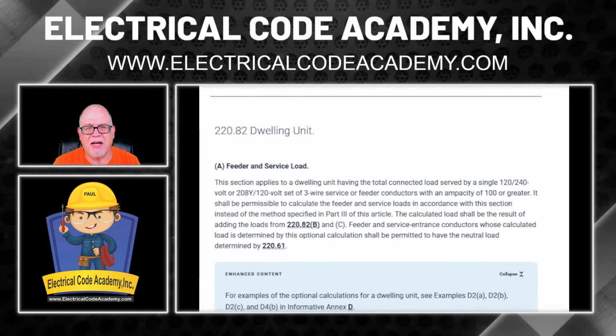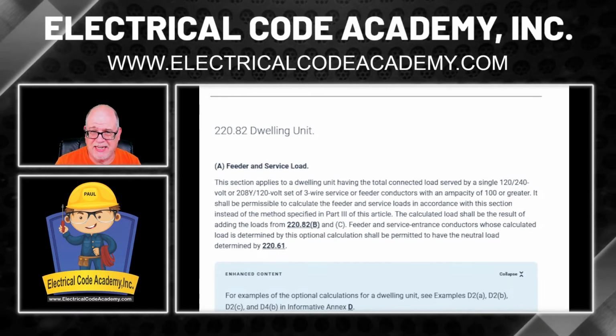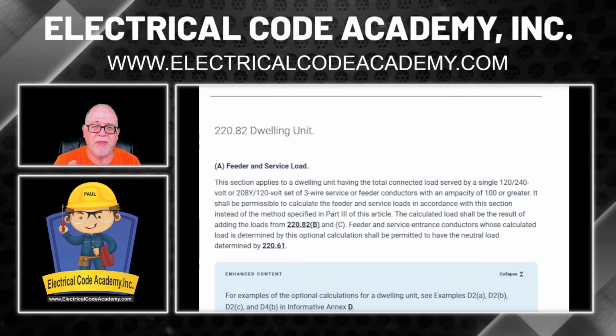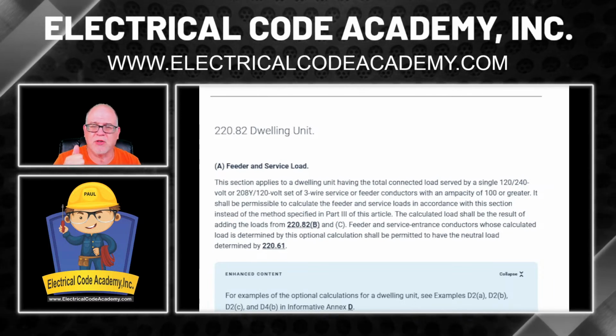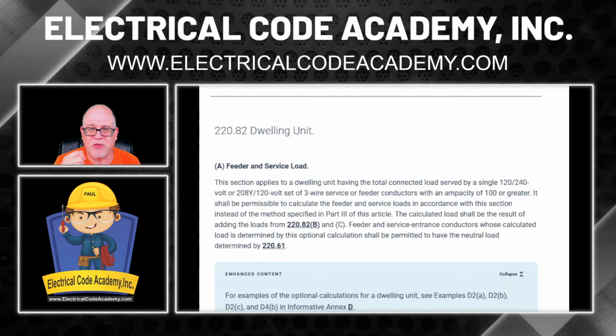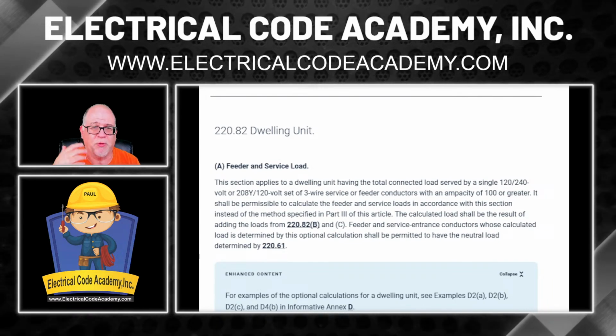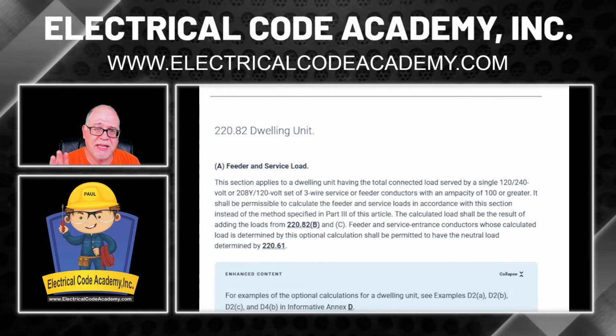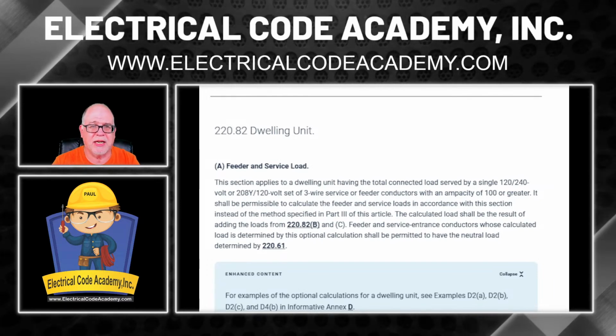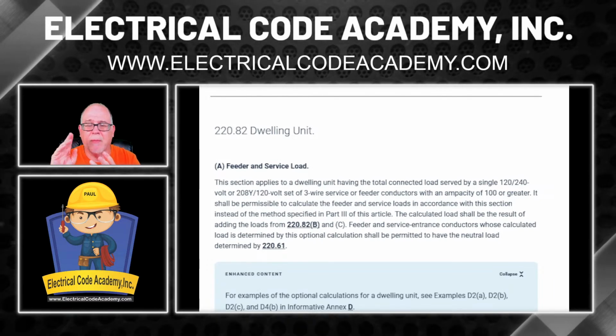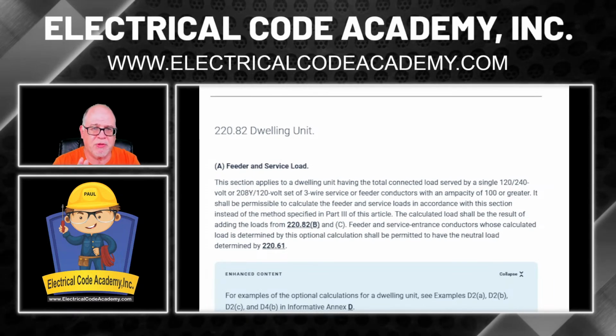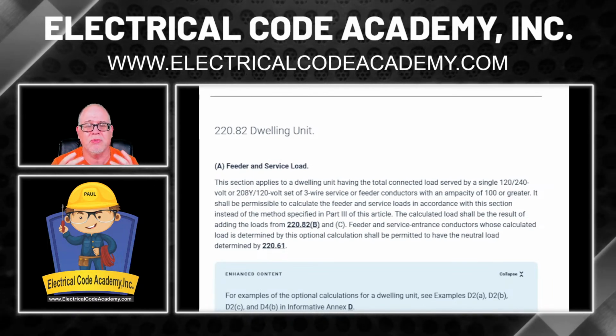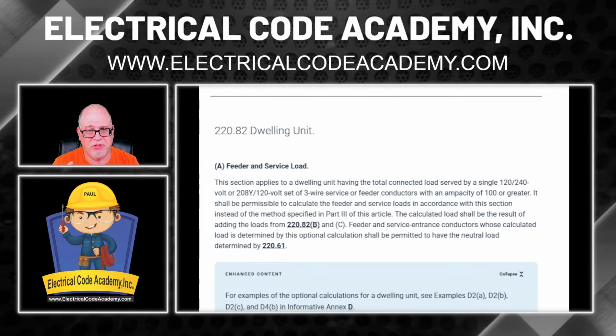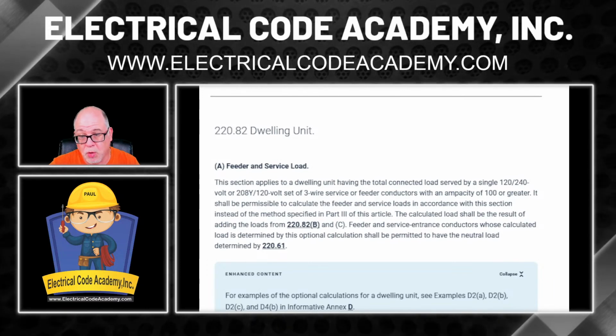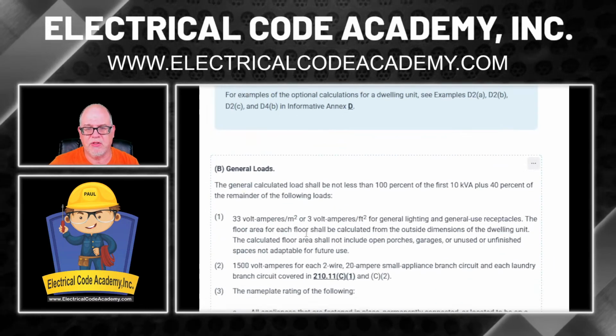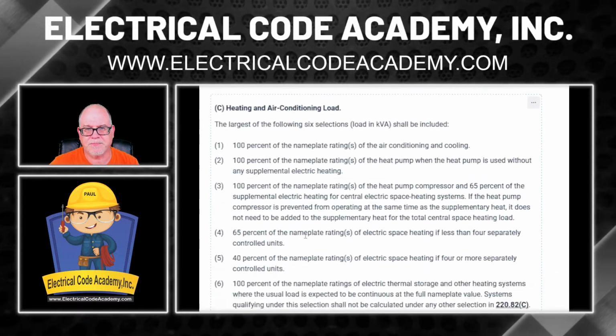This thing is broken down into an A, a B, and a C. B is going to be the one that deals with the 3 VA per square foot, talks about adding up all the nameplates, the first 10,000 at 100% and the remainder at 40%. We're not even doing any of that because we're not even looking at cooking. We're not even looking at appliances. We're not even looking at 3 VA per square foot. All we're being asked to do is deal with the heating and air conditioning, right? So we want to move on down to what we're working with in our question, and that is right here.